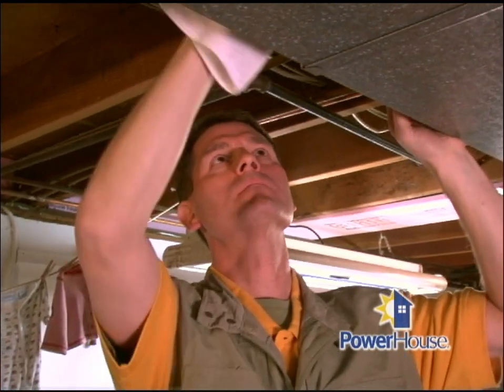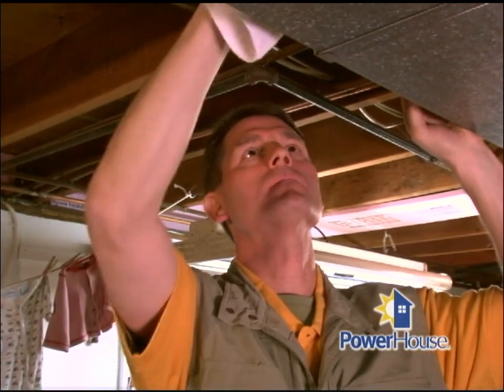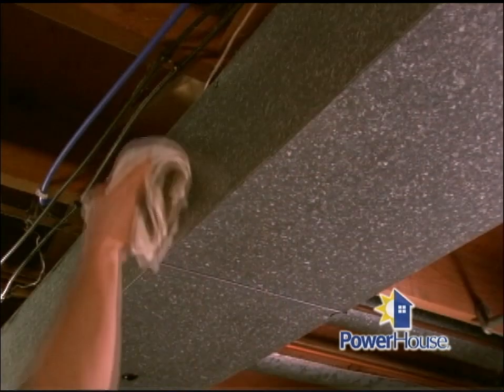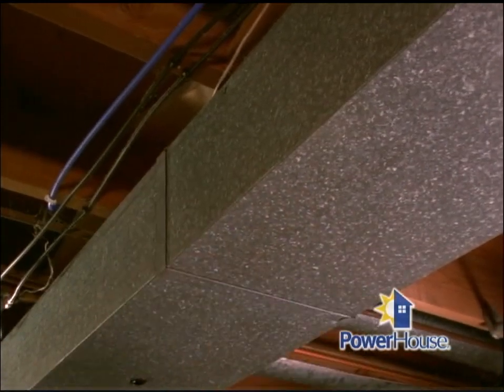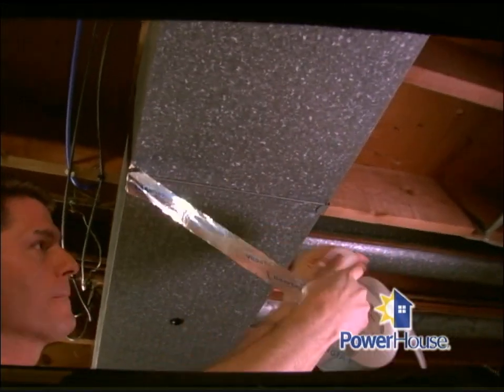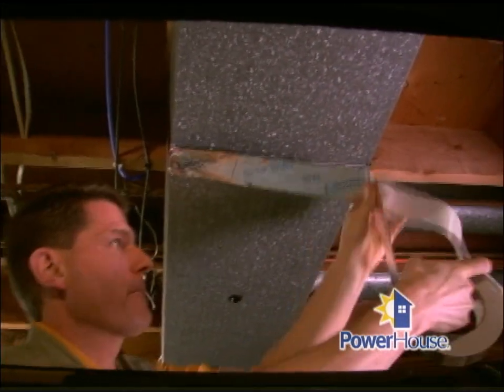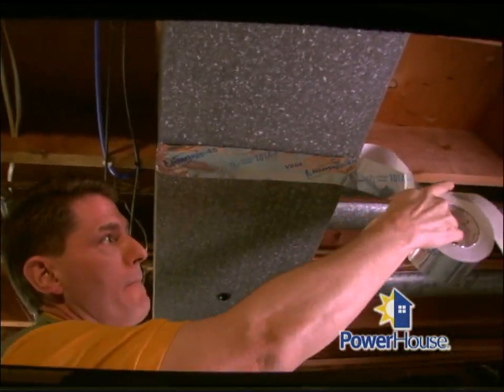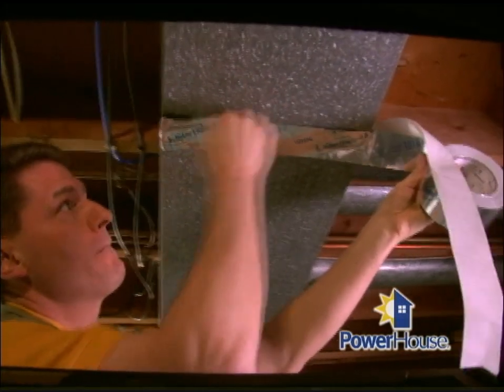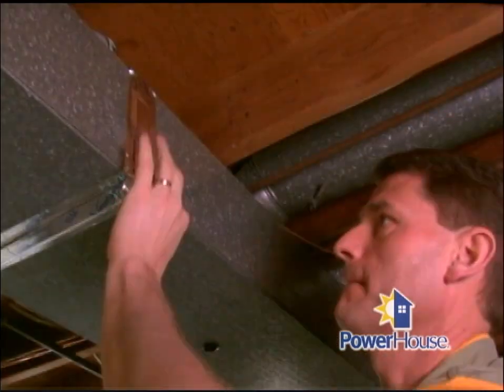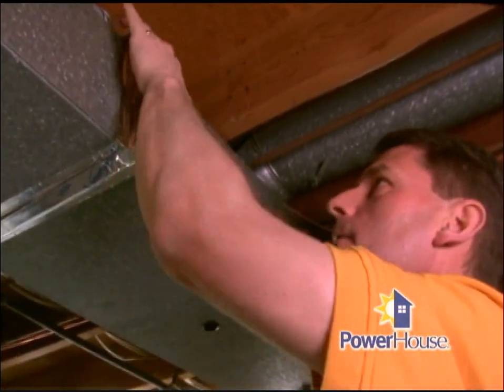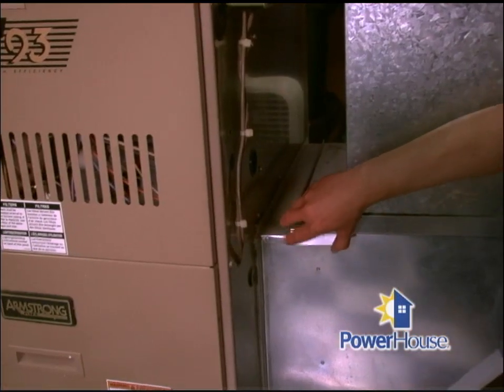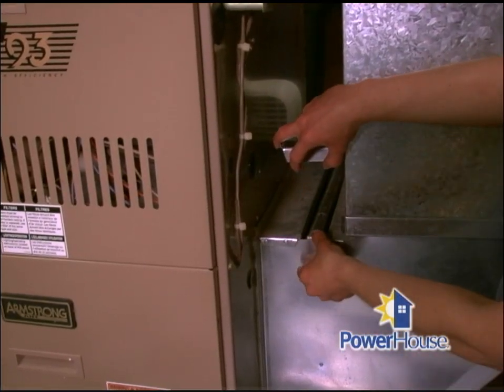Before you apply the tape, thoroughly clean the metal duct surfaces around all the joints and seams with a damp rag to remove all dust and dirt. Then carefully wrap the tape around the entire circumference of the joint and press firmly over the entire surface with your fingers to ensure that it completely adheres. And that's all there is to it. One note, do not consider the furnace filter slot or the combustion air inlets as gaps.